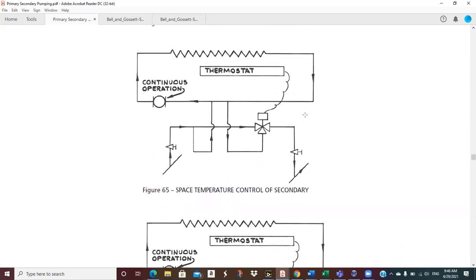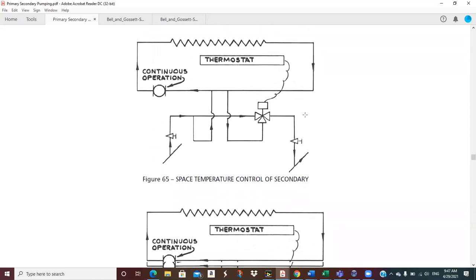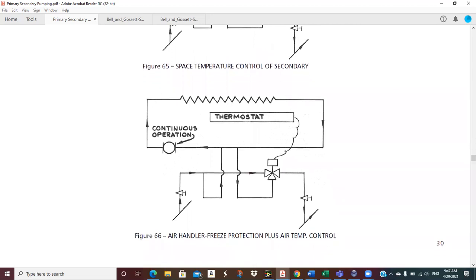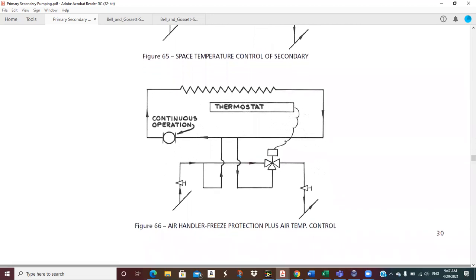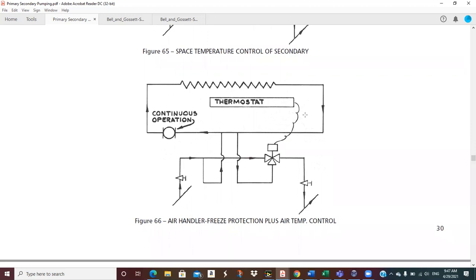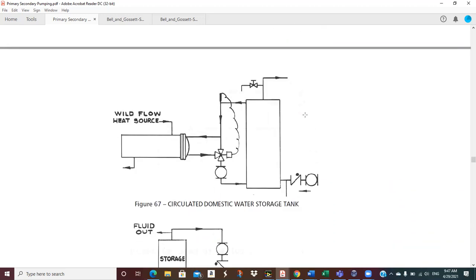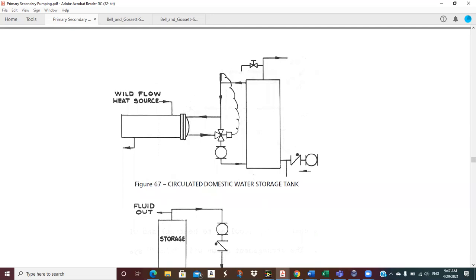Let's see. Space temperature control. What are we doing here? Oh, freeze protection. So, I mean, it's the same picture. Just the idea is that this is controlling discharge temperature from an air handling unit, and we get freeze protection because we're pumping the coil all the time. So this thing is kind of redundant in places.